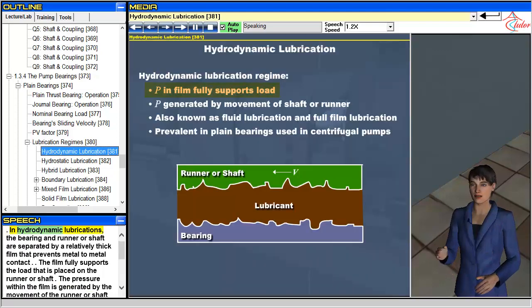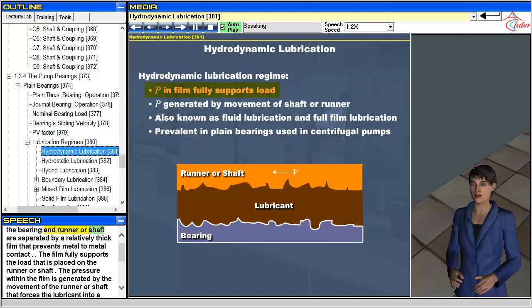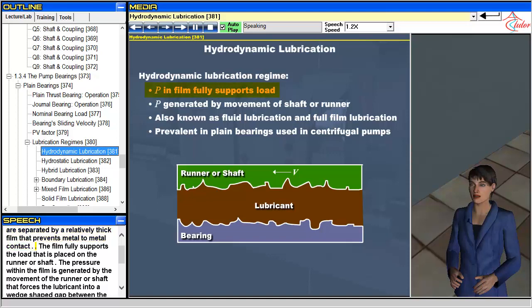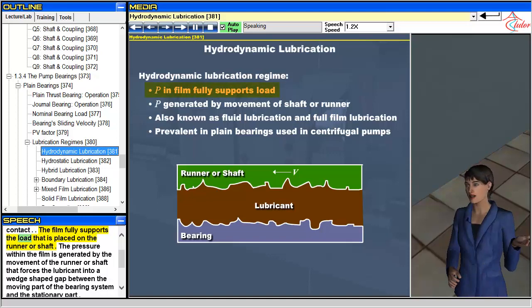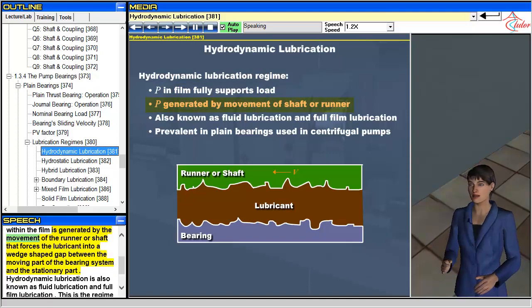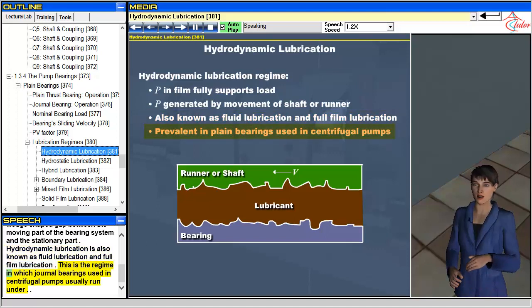In hydrodynamic lubrication, the bearing and runner or shaft are separated by a relatively thick film that prevents metal-to-metal contact. The film fully supports the load placed on the runner or shaft. The pressure within the film is generated by the movement of the runner or shaft, forcing the lubricant into a wedge-shaped gap between the moving and stationary parts. Hydrodynamic lubrication is also known as fluid lubrication and full-film lubrication, and is the regime in which journal bearings used in centrifugal pumps usually operate.